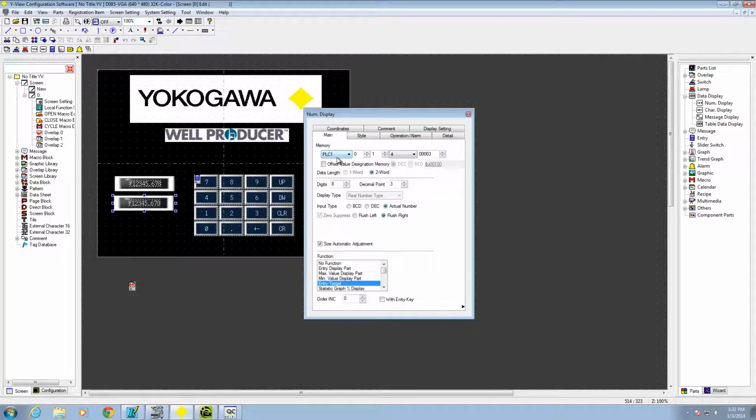So once again, it's PLC1, port 0, the unit ID, which is 1, and then it's going to be 400,003. In this case, these are the holding registers that I'm going to go ahead and write to. So once again, 2 words, actual number, 83 down here. These can change based on how big of numbers you're dealing with.